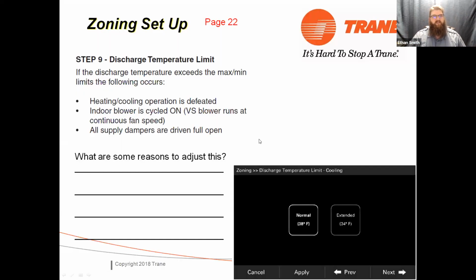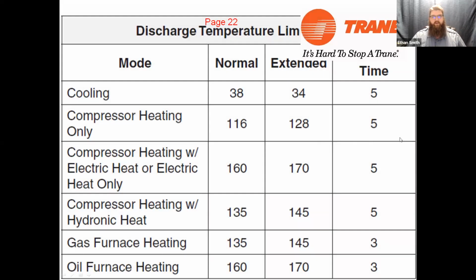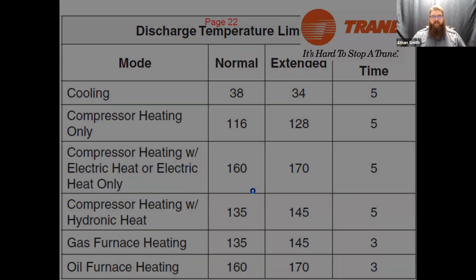Okay, discharge air temperature limits are just that. Here in Utah, where I live, we always use the extended range because our air is a little thinner. We struggle with these discharge air limits, so we use that extended range just to eliminate nuisance trips. You can choose whatever you want. This is a table, so there's a little cheat sheet here. Depending on what type of equipment you have, these are the options it will give you. You can be aware that the minimum off time for a furnace is 3 minutes versus 5 minutes for an outdoor unit. But normal versus extended ranges, like I said, I'm at altitude, so I always use the extended. If I'm at sea level, I'm probably going to use the normal. Just be aware of those options there for you guys.